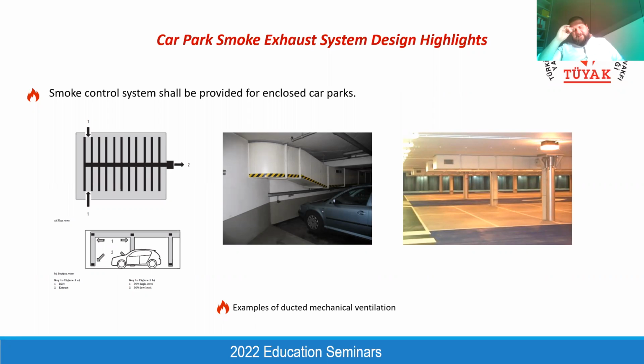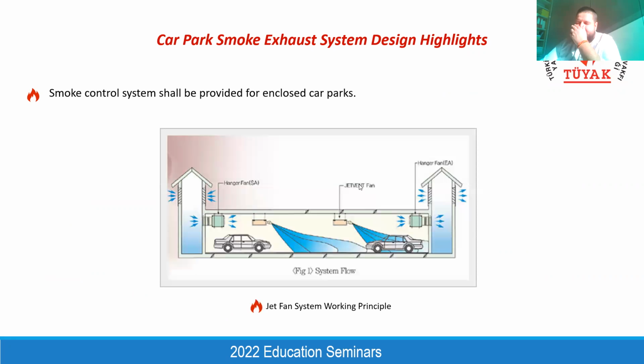Both of them have advantages and disadvantages, but I will try to explain the main differences between each of them. For the hard ducted system, you will have these kind of ducts all around your car park to exhaust the smoke and exhaust air released from the cars. And it causes a drop on the clear ceiling height. For the car park areas, you have a clear ceiling height, and if you provide a hard ducted system, you need to add the height of this duct onto the floor, and it ends up with higher floors, higher ceilings, and a smaller number of basement floors. That's why the optimization between the required clear heights and the required number of basement floors should be done by architects to decide which system will be used. And the second one is the jet fan system.